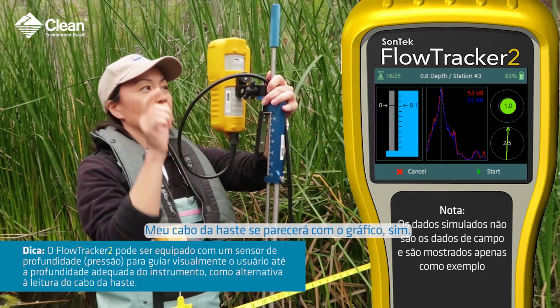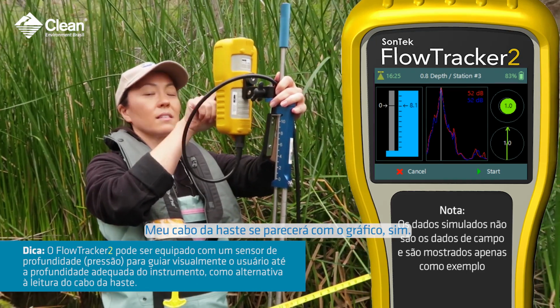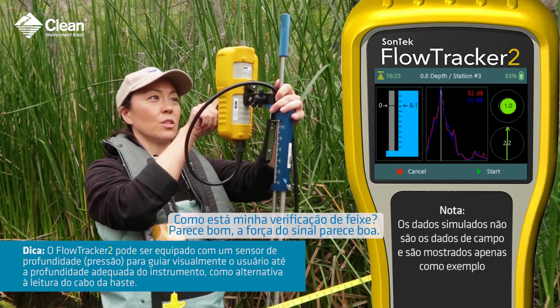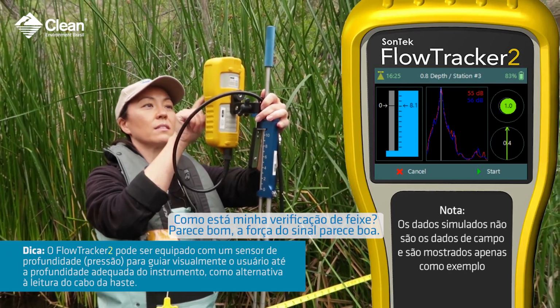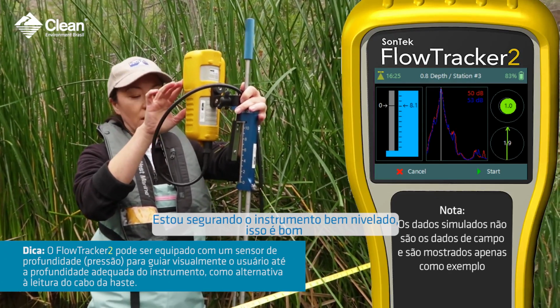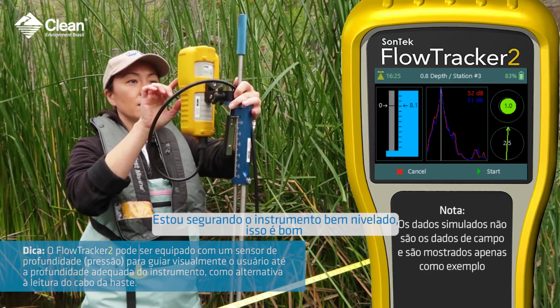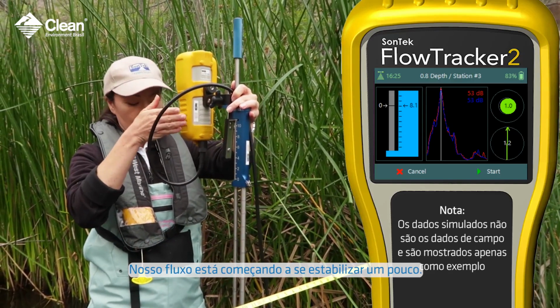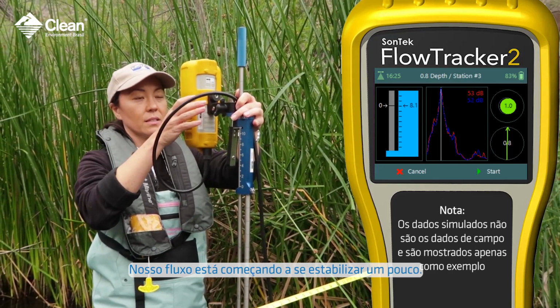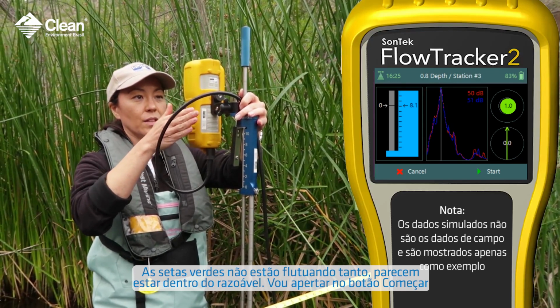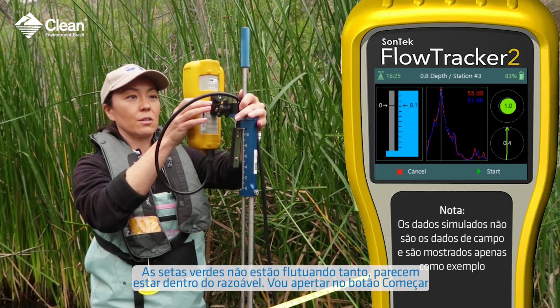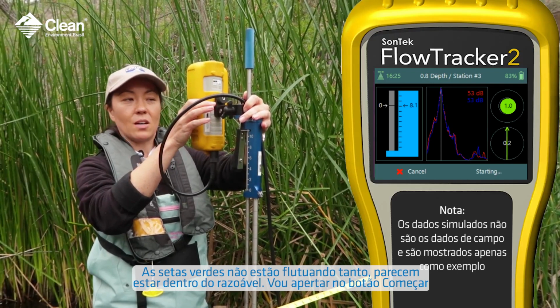Does my wading rod handle look like the graphic? Yes. How's my beam check? Looks good. Signal strength looks good. I'm holding the instrument pretty level. That's good. Our flow is starting to stabilize a little bit. The arrow's green and not fluctuating quite as much. Looks within reason. I'll hit start.